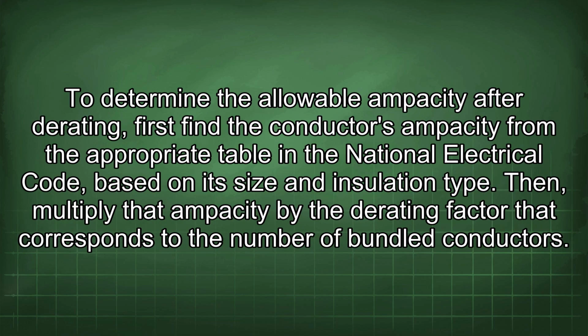To determine the allowable ampacity after derating, first find the conductor's ampacity from the appropriate table in the National Electrical Code, based on its size and insulation type. Then, multiply that ampacity by the derating factor that corresponds to the number of bundled conductors.